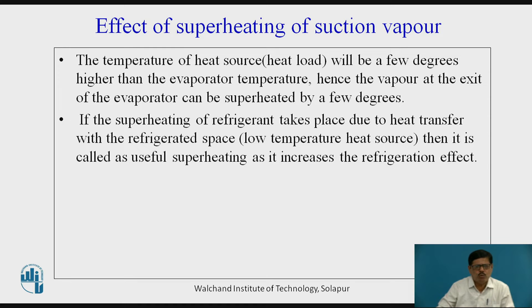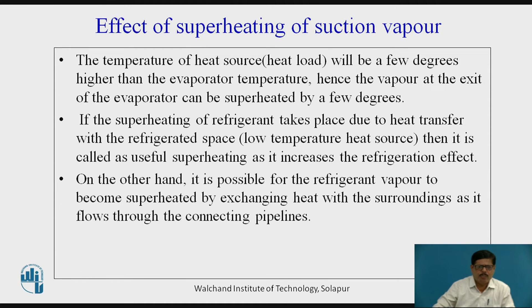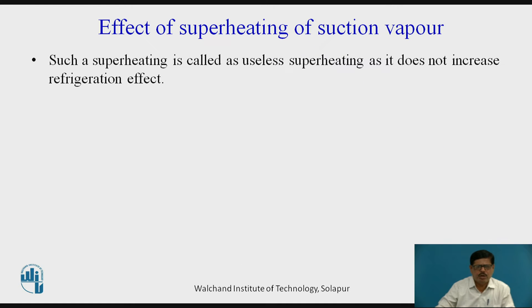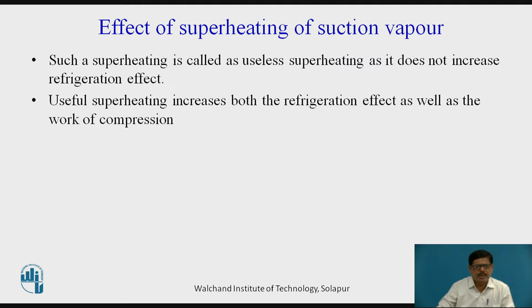It is important to note that if the superheating of refrigerant takes place due to heat transfer with the refrigerated space — that is, inside the evaporator — then it is called useful superheating, because it increases the refrigeration effect, as seen on the TS diagram as well as the PH diagram. But if the refrigerant vapor gets superheated by exchanging heat with the surroundings outside the evaporator — that is, in the connecting pipeline going to the compressor — then this superheating is of no use. Such superheating is called useless superheating, because it does not increase refrigeration effect. Useful superheating increases both refrigeration effect and work of compression.